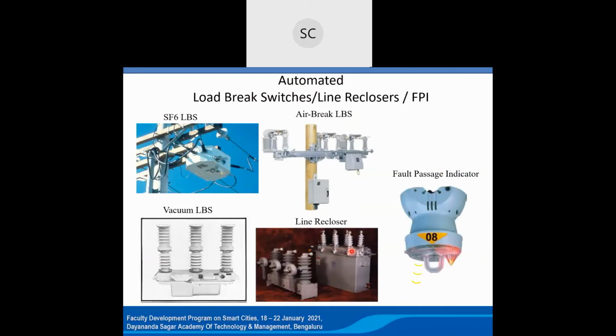Again, if something happens within more than 1 minute, one more trip happens. Again, it will wait, for 3 shots. Now at this stage, let us assume there is a permanent fault. When a permanent fault happens, the first time it tripped, it waited for 1 minute. And again, at the end of 1 minute, it will try to reconnect. Due to the permanent fault, immediately after reconnection, again it will trip because fault current exists. So again it will wait for 1 minute. Then it will try to connect.